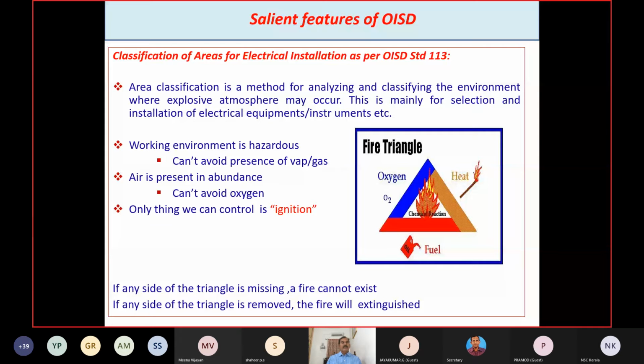the exhaust pipe. Inside, if you go to some bottling plant, you can see the mastic flooring. That's mainly to avoid generation of any spark due to accidental falling of metal objects. And for maintenance purposes, they will use non-sparking tools, and flame-proof and intrinsically safe equipment will be used inside. So all these measures are taken for elimination of ignition sources. In spite of that, we cannot ensure 100% elimination of ignition source, because it may be generated at any point of time. For example, the hidden thing of static electricity and lightning, and even a nail in your shoes may create a spark.